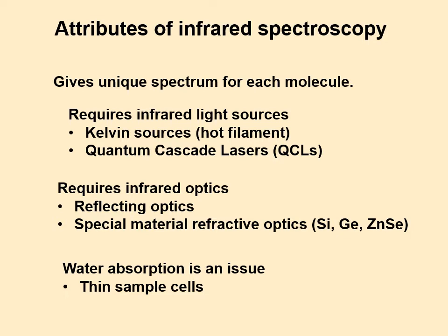To summarize infrared spectroscopy: it gives a unique spectrum for each molecule, which is fantastic. It requires different kinds of light sources because this is all in the mid-infrared. You can use a Kelvin source — a red-hot glowing filament, not very expensive but not very bright — or a quantum cascade laser, which is expensive but provides higher intensity tunable light.